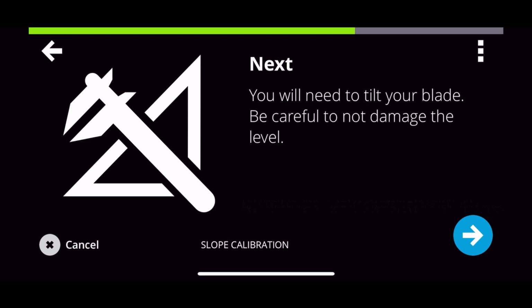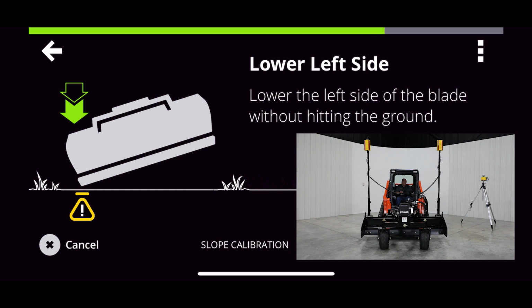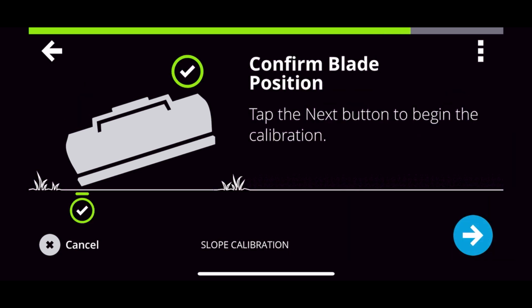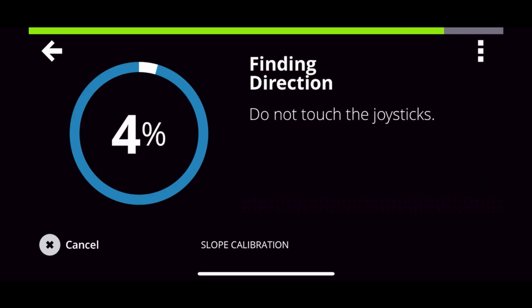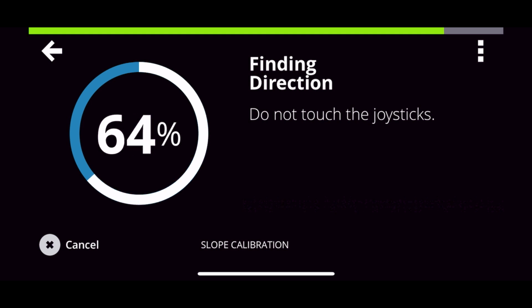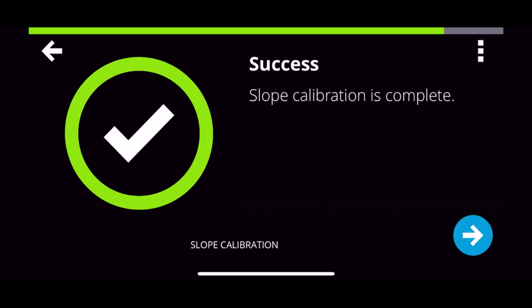Now we're going to work on setting the slope calibration. The next thing we'll need to do is lower the left side. Continue on here with our deal. We'll need to put our blade down so that the corner is touching, like so. And then we will run the calibration and confirm this point. This will take a few seconds. And when that is confirmed, we are done with that, and we can hit next.